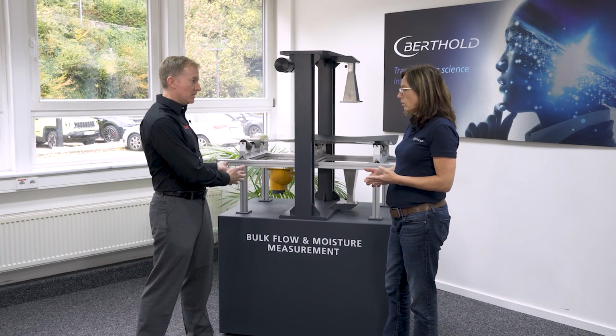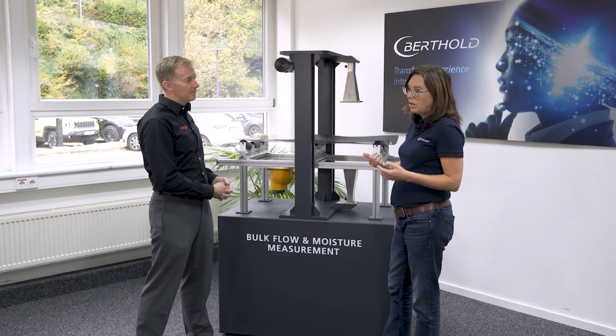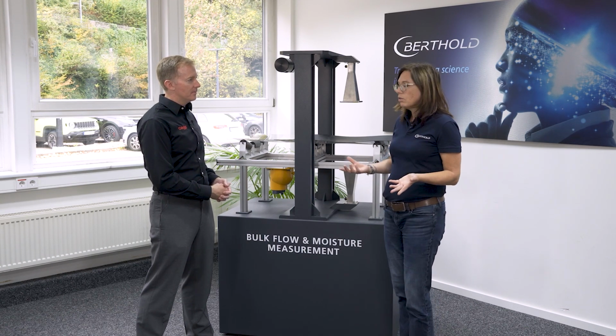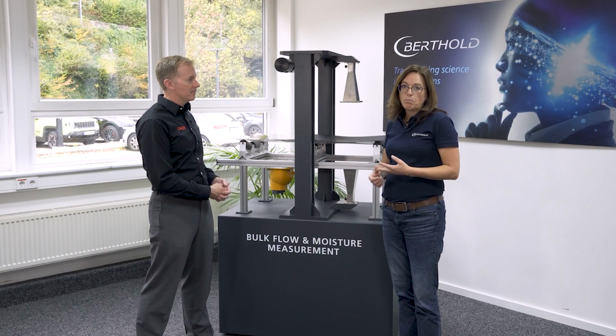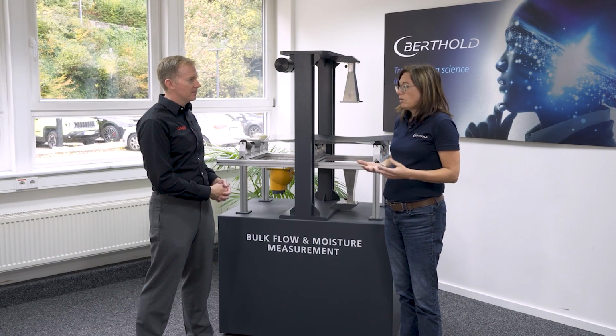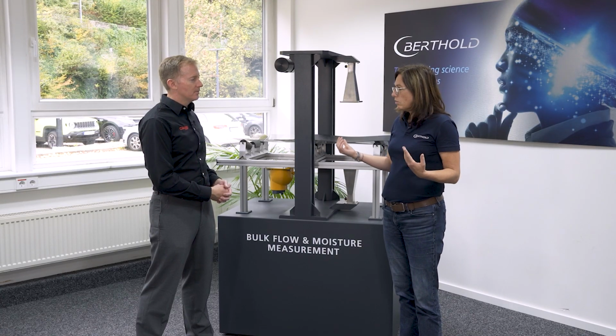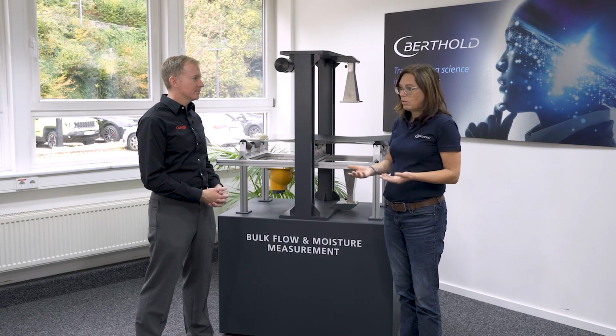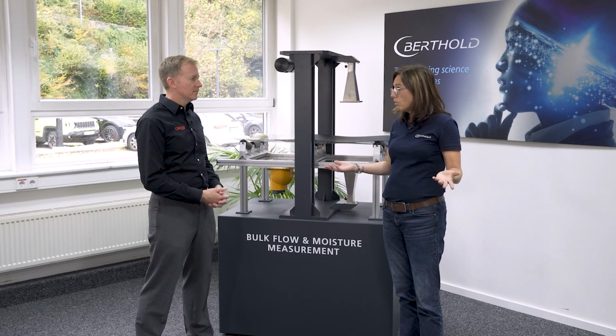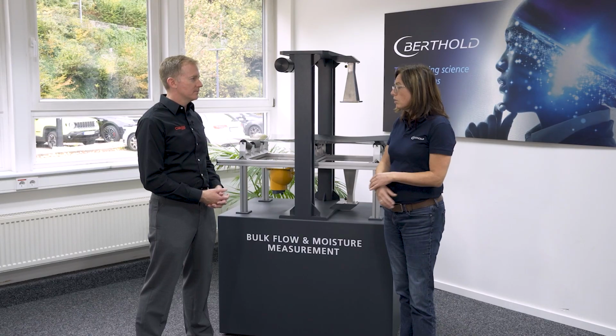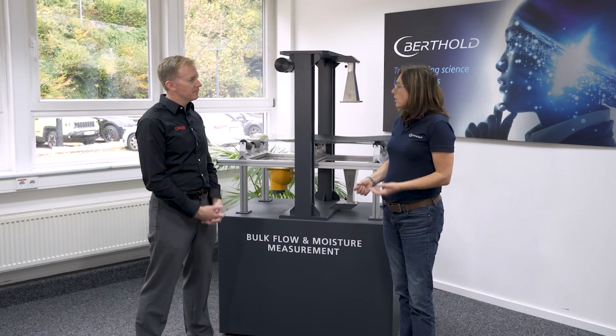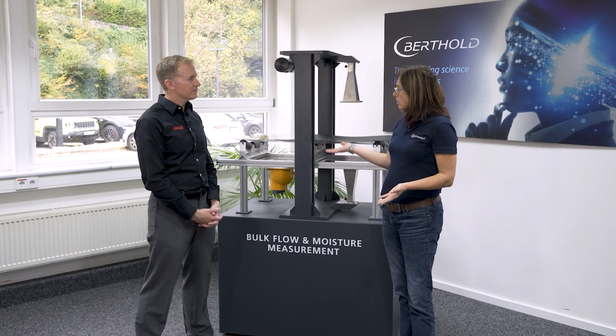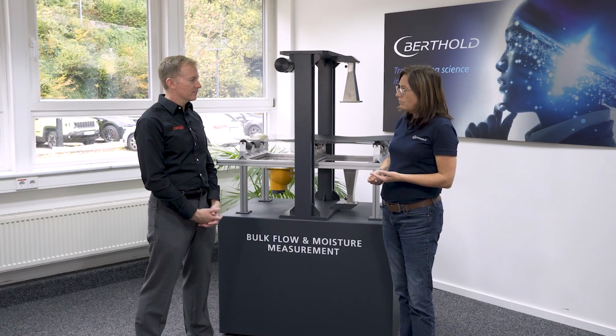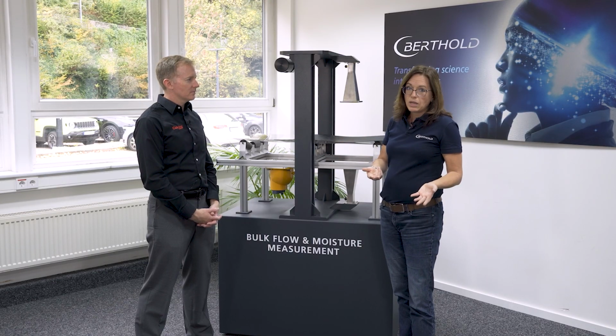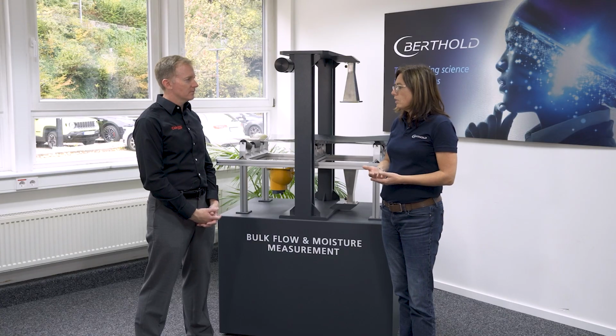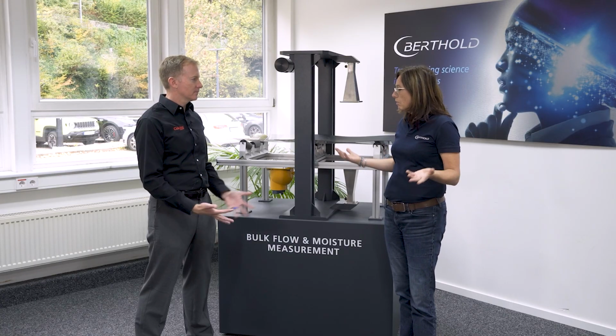I think you talked about speed, right? Yes, the instrument requires a speed signal. This can be from a tachometer or a known velocity the belt is running. This can be given to the instrument by a current input, for example, or a pulse input - we also have that. By measuring the area weight of the material on the belt, combined with this velocity signal, we can easily give the customer tonnage, meaning the mass flow.